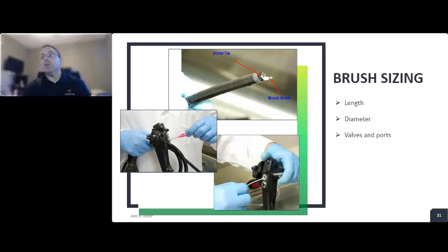Or even if you're doing a pull-through style where you're pulling that through and feeding back in, we need to clean that brush off over and over again, like we read in the regulatory, so that we know that that is clean and there's nothing left on that brush. Regulatory does a good job. The manufacturers' IFUs do a good job of describing those steps and making sure there's nothing dirty or left, right? That rinse and repeat.